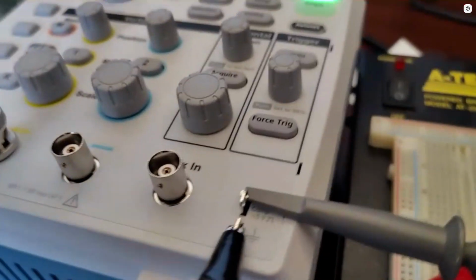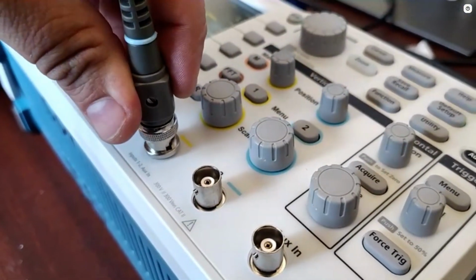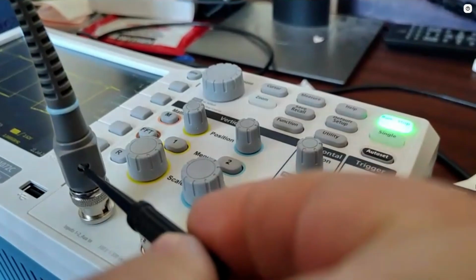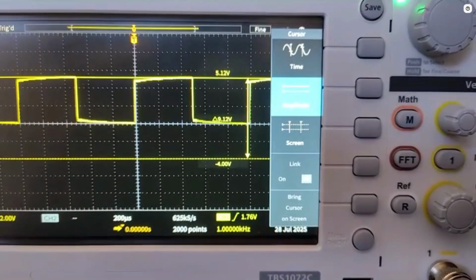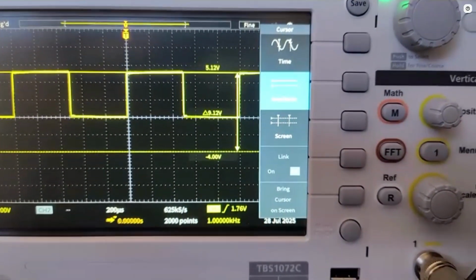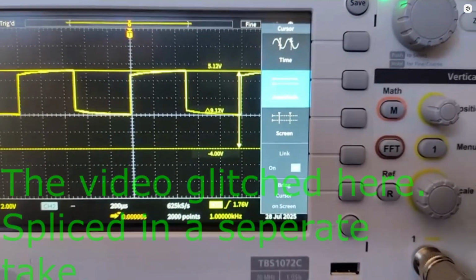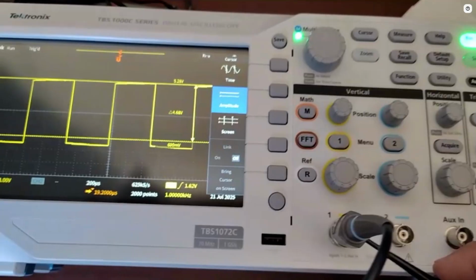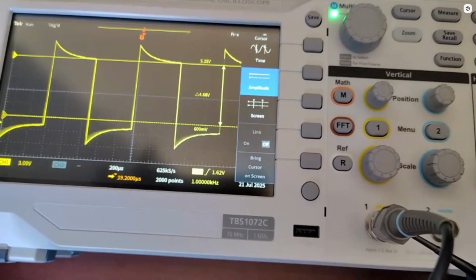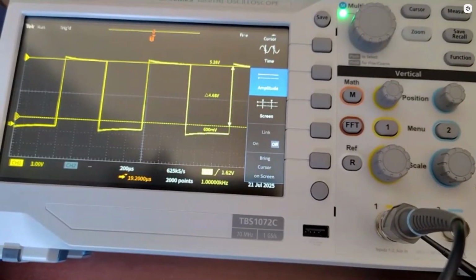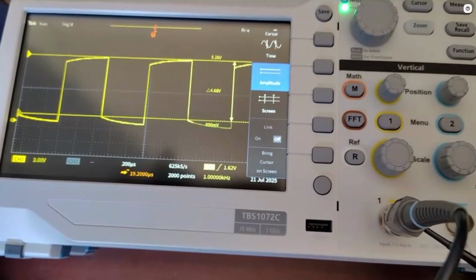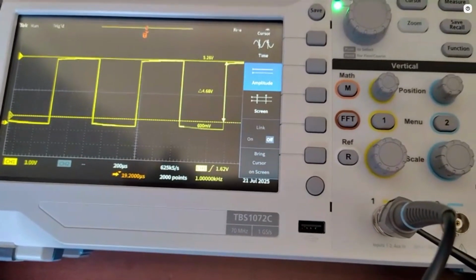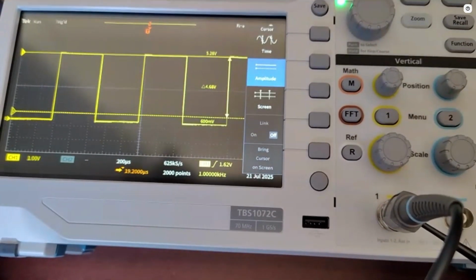I'm going to come down to my probe, to that little screw right there, and put my compensation tool in. As I adjust it, I'll make it worse first as it climbs up to the top, then I want to adjust the waveform so it comes down flat. One direction makes it worse going up, then I go the other direction to make it smaller, and eventually it overruns and zeros back. What we want is that square waveform to be as flat as possible.